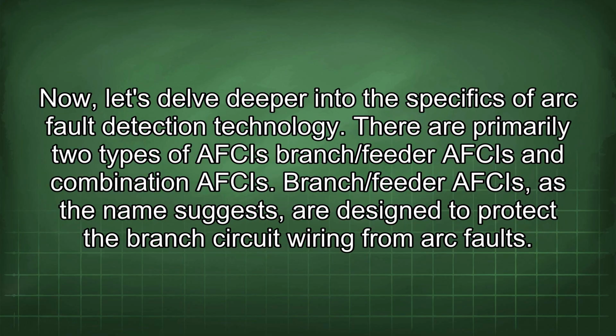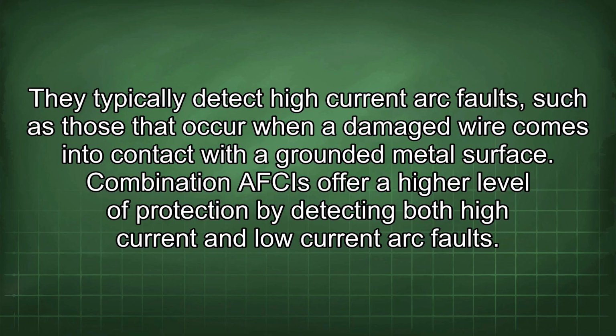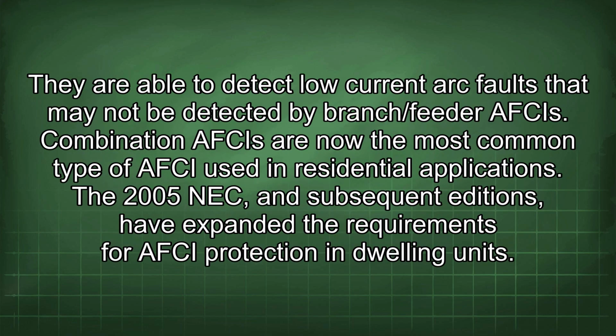Now let's delve deeper into the specifics of arc fault detection technology. There are primarily two types of AFCIs: branch/feeder AFCIs and combination AFCIs. Branch/feeder AFCIs, as the name suggests, are designed to protect the branch circuit wiring from arc faults. They typically detect high current arc faults, such as those that occur when a damaged wire comes into contact with a grounded metal surface. Combination AFCIs offer a higher level of protection by detecting both high current and low current arc faults. They are able to detect low current arc faults that may not be detected by branch/feeder AFCIs. Combination AFCIs are now the most common type of AFCI used in residential applications.